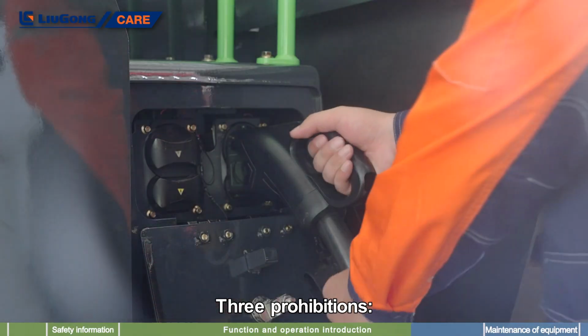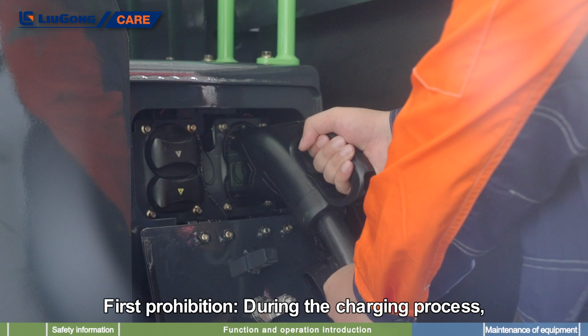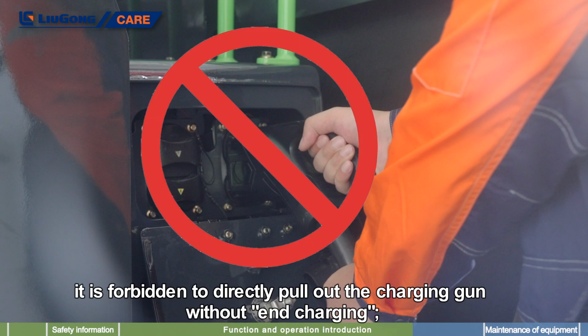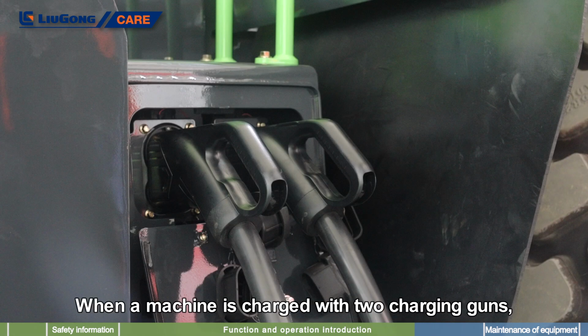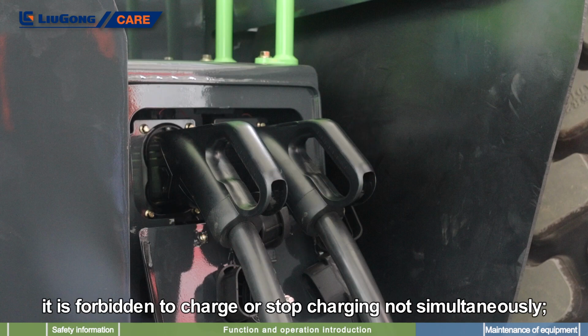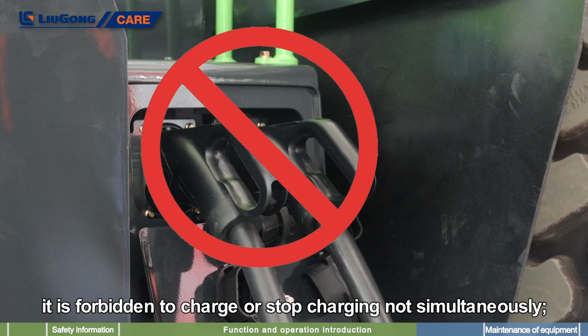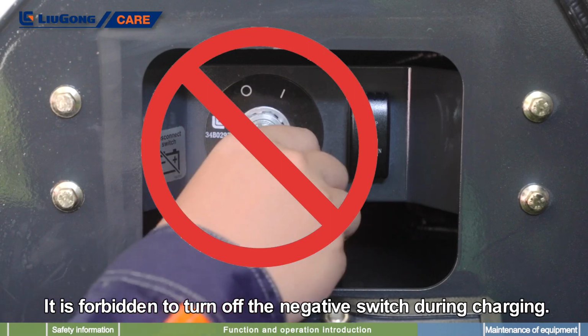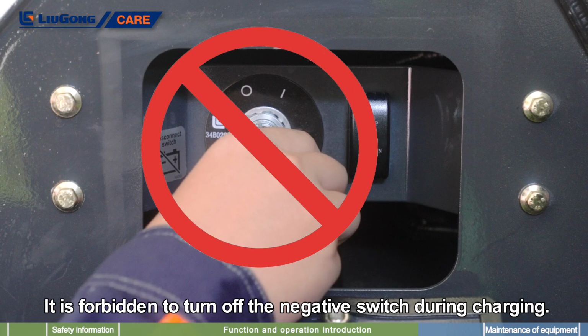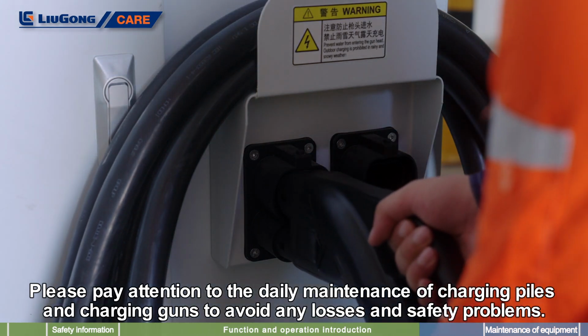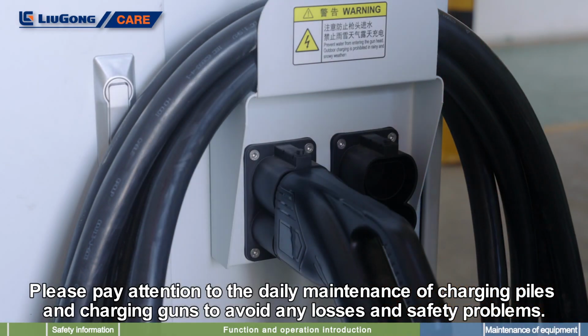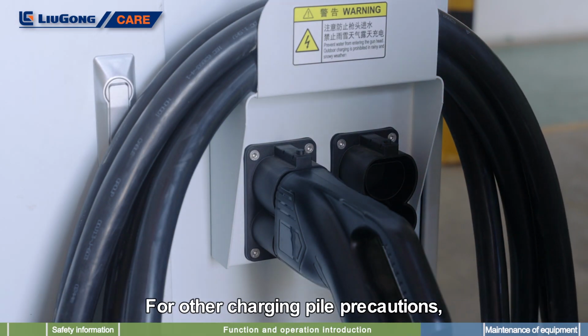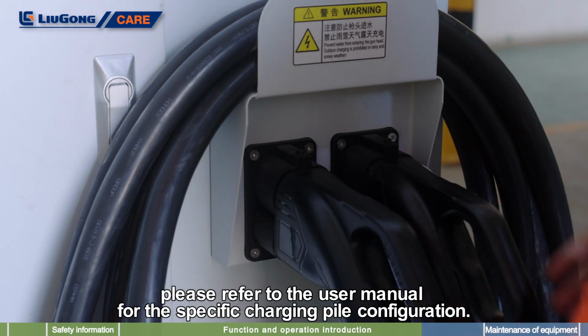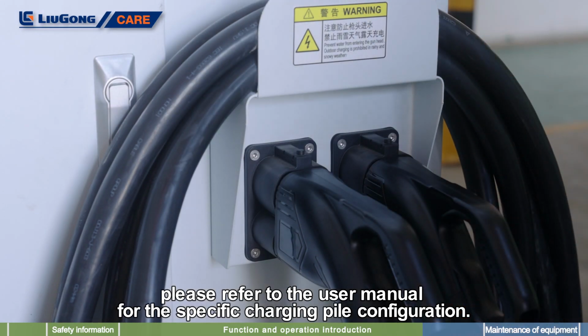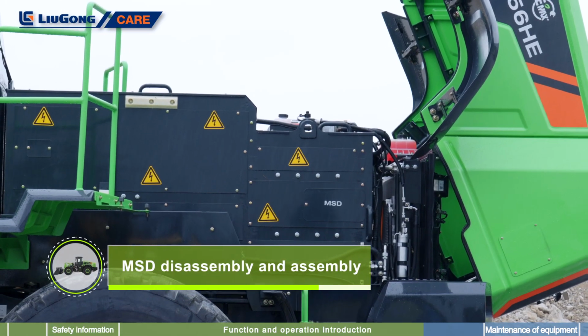3 prohibitions. First prohibition. During the charging process, it is forbidden to directly pull out the charging gun without uncharging. Second prohibition. When a machine is charged with 2 charging guns, it is forbidden to charge or stop charging not simultaneously. Third prohibition. It is forbidden to turn off the negative switch during charging. Please pay attention to the daily maintenance of charging piles and charging guns to avoid any losses and safety problems. For other charging pile precautions, please refer to the user manual for the specific charging pile configuration, MSD disassembly and assembly.